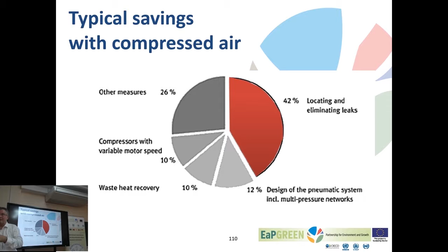And 1 millimeter is the smallest hole I can identify just by listening. For smaller holes, I need ultrasonic equipment to identify. So to check the plant when it's down on a Saturday or in the evening when operations have stopped, to mark leaks and to seal the leaks is really a profitable exercise usually.